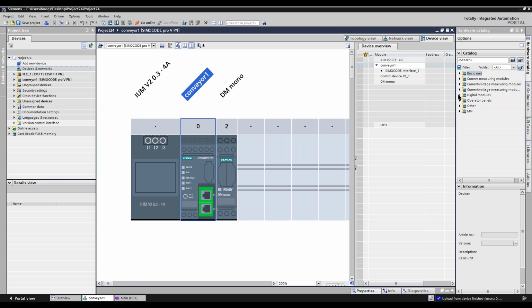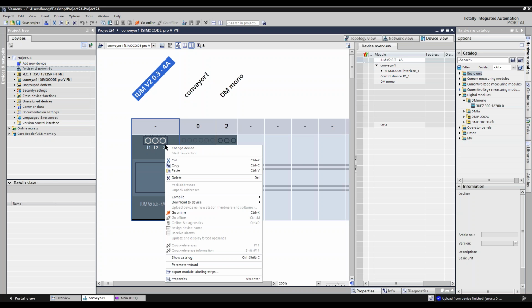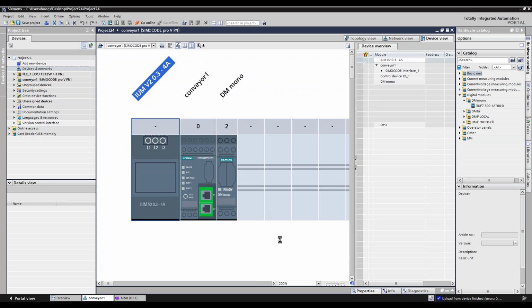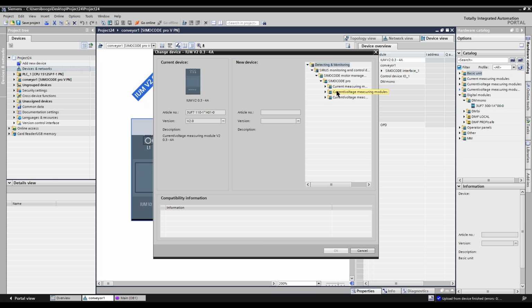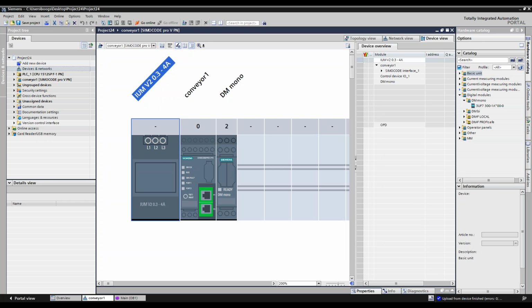Now, if I wanted to add on another one, I could go here and say, I'm going to add on another digital module, and that's just drag and drop. Or if I needed to replace this and say, I'm only going to do current module, then I would click on it and just say change device. And then I would go pick and say, I'm going to do current measurement only. So I drop that down, and then I pick the current measuring, and it will replace it automatically. Okay, that's if I was looking at it in the field and it's already been programmed.